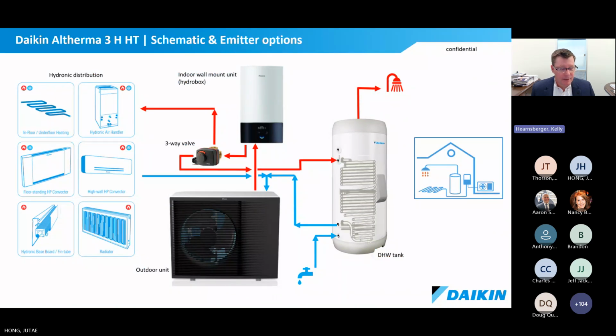A little bit on the mechanics of how things work, and I'll just demystify the system here up front. We do not do all of those things simultaneously. We do have advanced systems in VRV that are capable of serving hot water, low temp, if you will, and then heating and cooling simultaneously. But in this particular system, there is a priority set at the setup of the system. And you can see here on the bottom, of course, we've got our outdoor unit. And at the top, there's a head unit, or what we call an indoor wall mount unit, or a hydro box. That's typically more of a manifolding system with the brains of the unit in the head of the system.